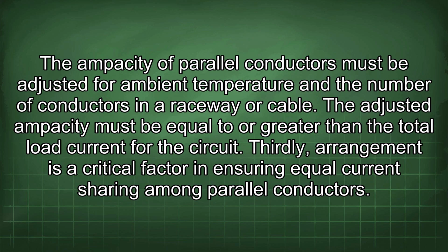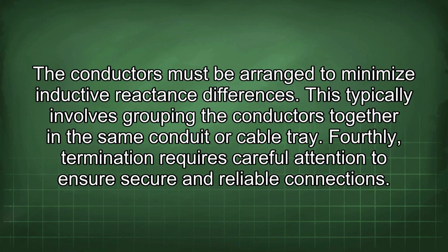Thirdly, arrangement is a critical factor in ensuring equal current sharing among parallel conductors. The conductors must be arranged to minimize inductive reactance differences. This typically involves grouping the conductors together in the same conduit or cable tray.